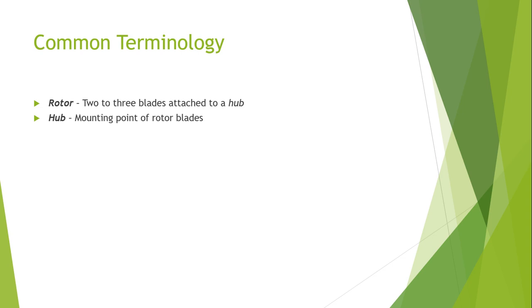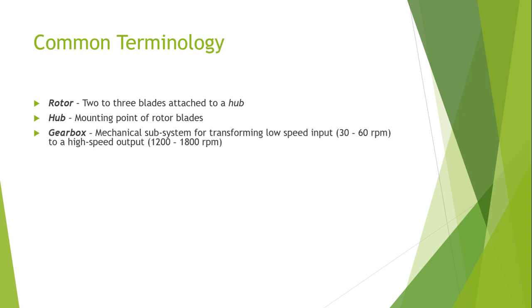The hub is the mounting point for the rotor blades. Then there is the gearbox, which is a mechanical subsystem for transforming a low-speed input — say 30 to 60 revolutions per minute — to a high-speed output using a gear mechanism.